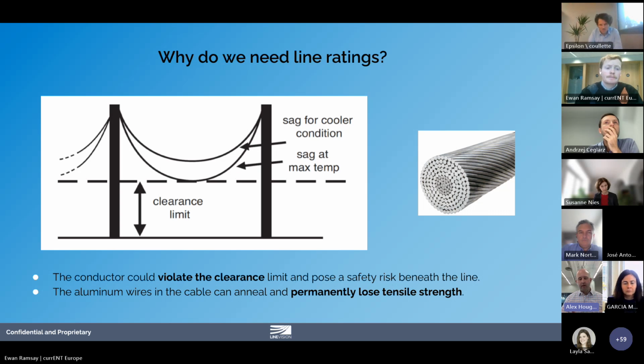And then there is a standpoint of damage to the asset itself. So if a line gets too hot, the molecular structure can change and it can anneal, and that results in permanently damaging the asset itself. So it's losing tensile strength, which will not allow it to move as much power. It'll also continue the sag. So really you have to be very careful about how you are loading this line so you don't exceed those limits. Next slide.